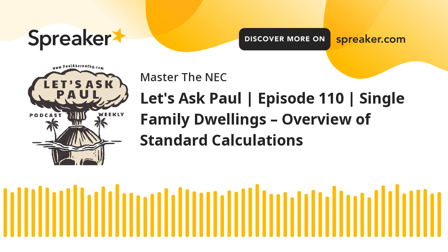All right, next is the household electric cooking appliances. As long as they're over 1 3/4 kW or 1,750 watts or VA, however, as long as they're over that, then you can use the allowances of 220.55, okay? Now, 220.55 is an interesting table, and you're basically going to use column C in all cases, unless your cooking equipment happens to fall under column A or B, okay? And you're going to always compare A and B to C, right, if note 3 is applicable.